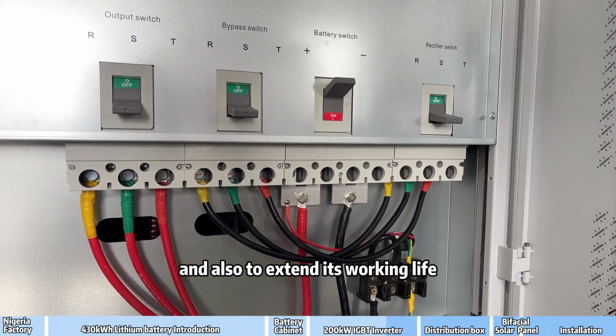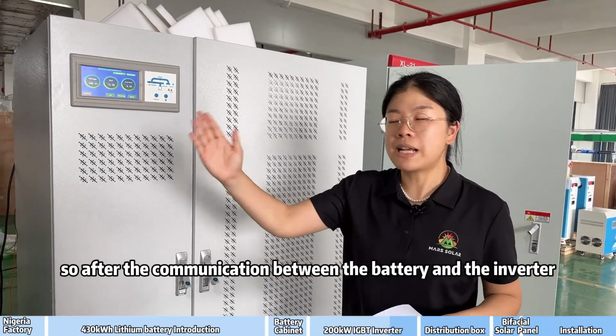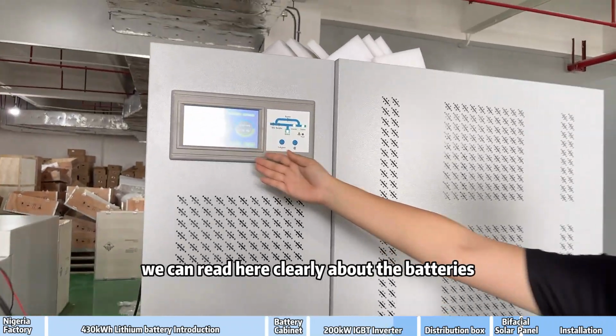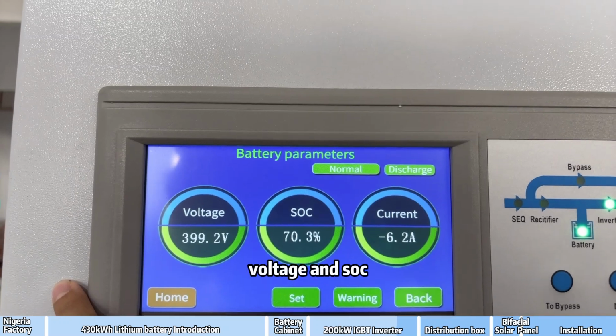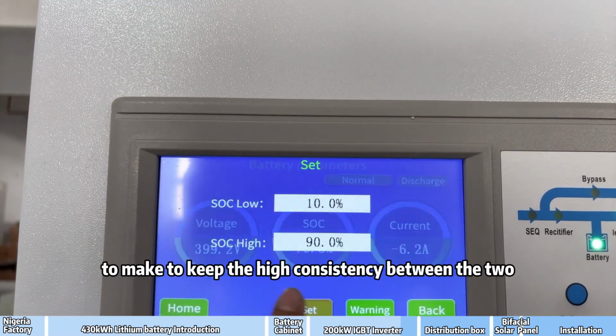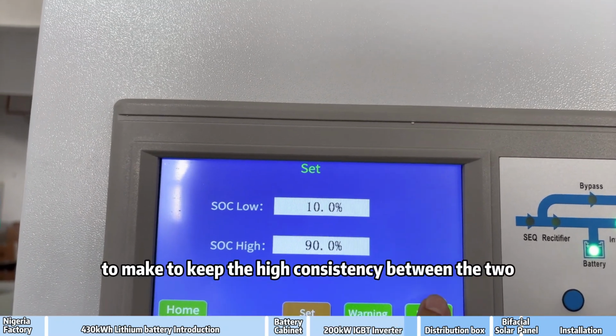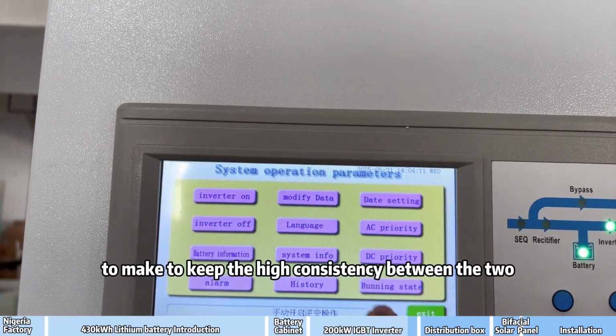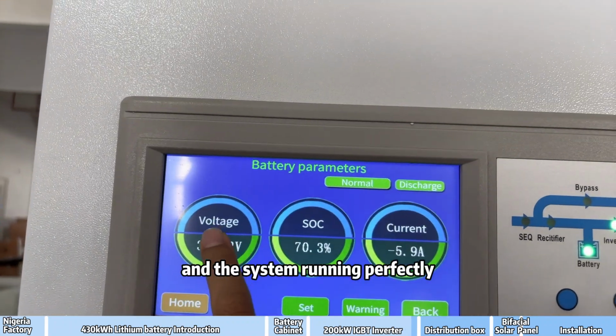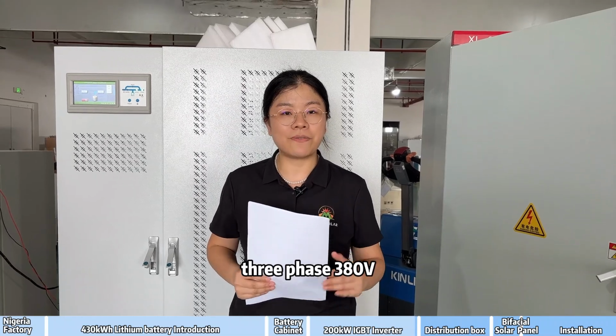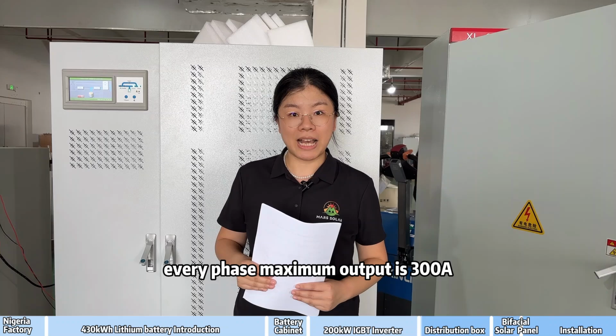After communication between the battery and inverter, we can read here clearly the battery's voltage, SOC, and working current, keeping high consistency between the two so the system runs perfectly. Total output is 200 kilowatts, 3-phase, 380 volts, with every phase's maximum output 300 amps.